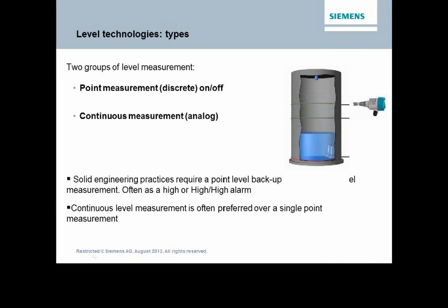If we have a number of discretes, we tend to get closer and closer to a continuous measurement, and that's where analog devices come in, where we're actually measuring and getting to know what the level or process is doing at any given point in time. These discrete and analog measurements could be temperature, or a simple flow rate, but solid engineering practices generally combine both analog inputs and discrete inputs. So for the applications we'll be looking at, quite often we use a continuous measurement in an analog mode along with a discrete point measurement.